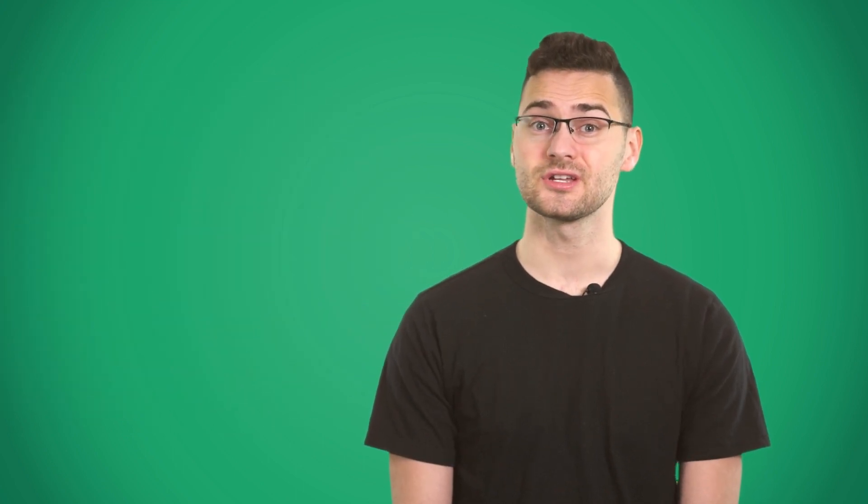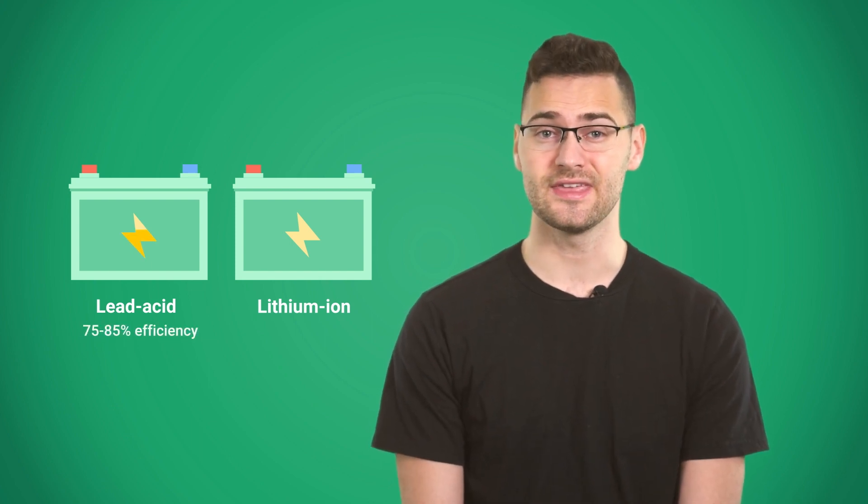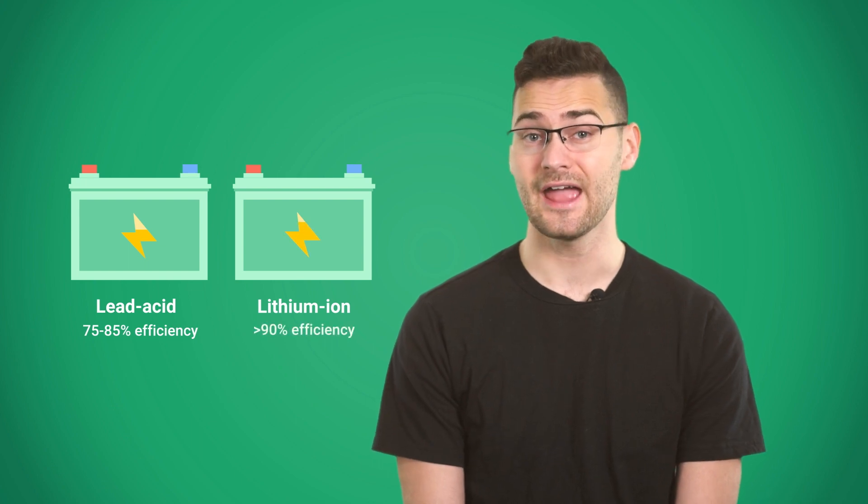They are also more efficient. Lead acid batteries store and transfer about 75 to 85 percent of energy that they get, whereas the efficiency of lithium ion batteries is at 90 percent or higher.